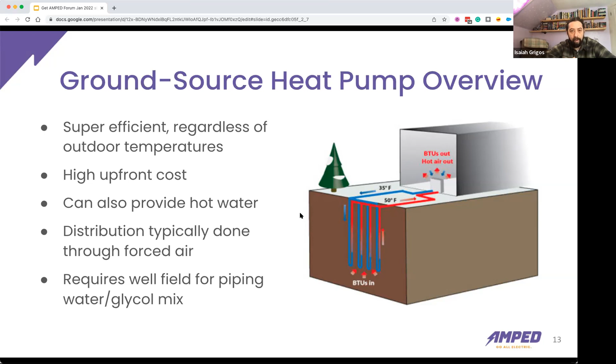It's not free heat. There is a lot of pumping power involved, and basically, you need to make sure your system is well designed, and you need to make sure you have land for it. Basically, you have all these outdoor wells that you're pumping a glycol mix through, and it takes a lot of power to pump that glycol mix through to steal heat from the ground. So make sure if you're evaluating ground source heat pumps, you consider the upfront cost, a good design, and the fact that you're going to need various wells dug throughout the property. Next slide.